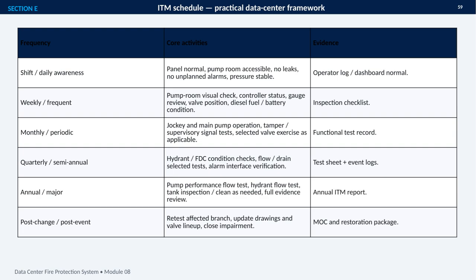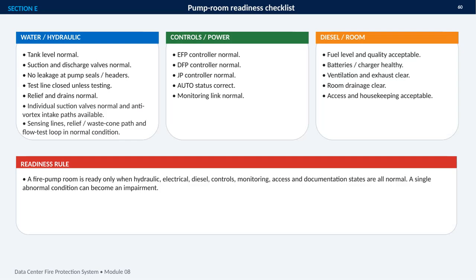review. Finally, after any change or event, the affected branch must be retested, drawings and valve lineups updated, and the impairment formally closed. Every activity needs documentation, from operator logs and checklists to functional records, event logs, and the annual ITM report. This slide provides a practical pump room readiness checklist, organized around 3 areas: water and hydraulic conditions, controls and power, and the diesel equipment and room itself.